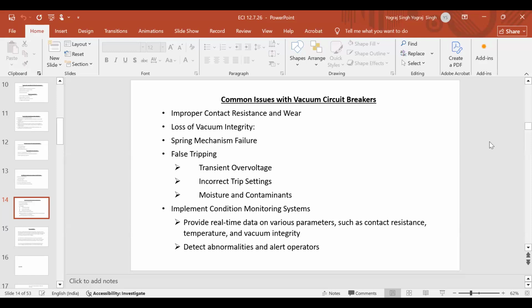Achha, now incorrect trip settings, there is one thing which I want to tell. Fault isolation depends on the relay setting. The relay is actually the brain of a circuit breaker. Circuit breaker in itself is nothing. So you need to have a battery bank which provides supply to the relay. The relay senses the current. When there is overcurrent, whether it's an overload or a short circuit, it sends a signal and accordingly the system trips. The relay itself doesn't have any tripping mechanism, but it senses the current and sends a signal to the tripping coil. So that makes it trip or otherwise.